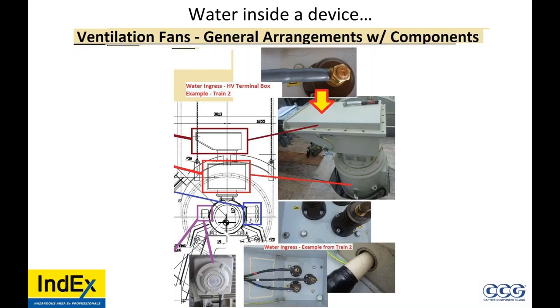How did the water get in there? Well, they have a little anti-condensation pack, which is not enough for certain locations in the world where there's 100% humidity. Also, there's clear indication on the bolt holes that water was getting in through the bolts. So perhaps the manufacturer, the testing laboratory, perhaps they both made multiple errors on this.